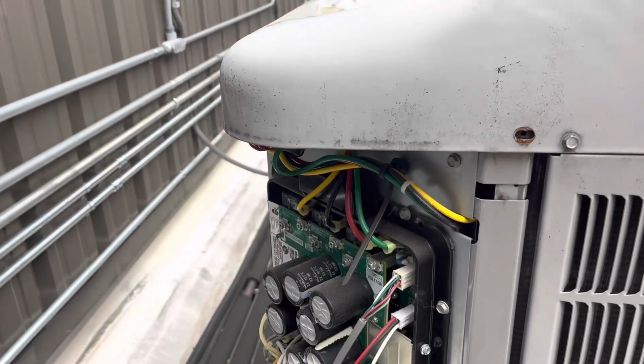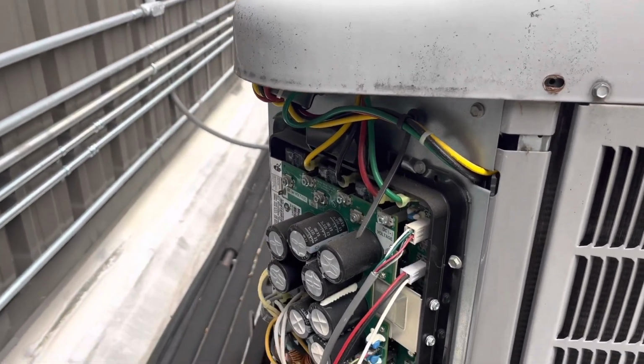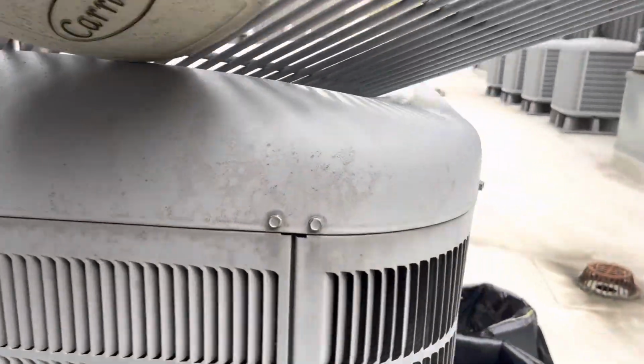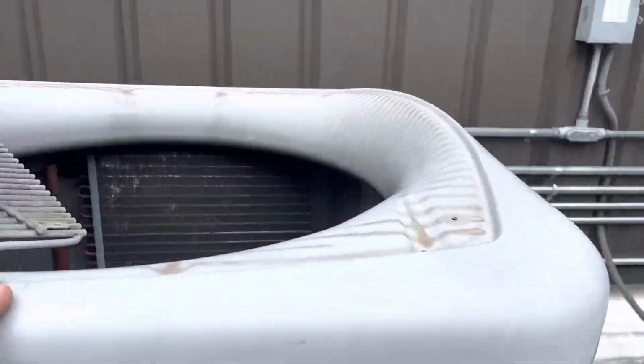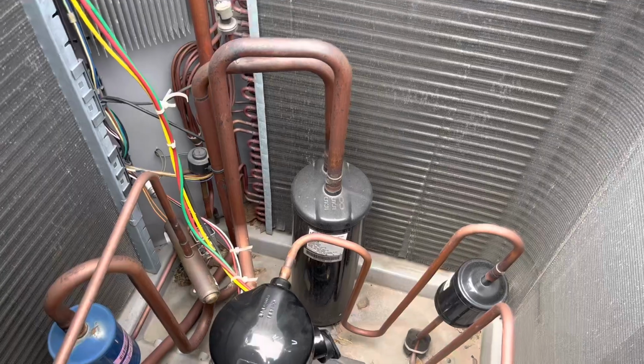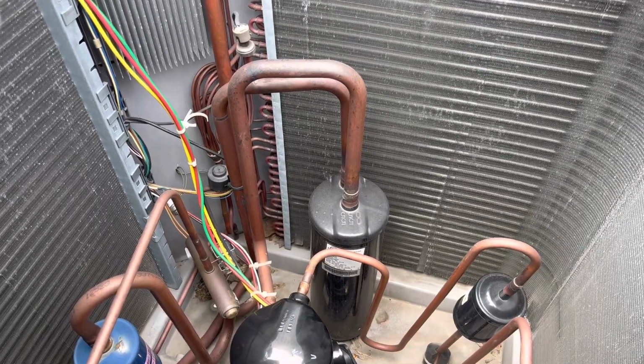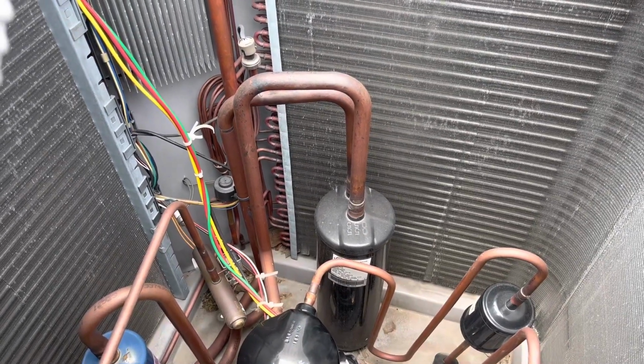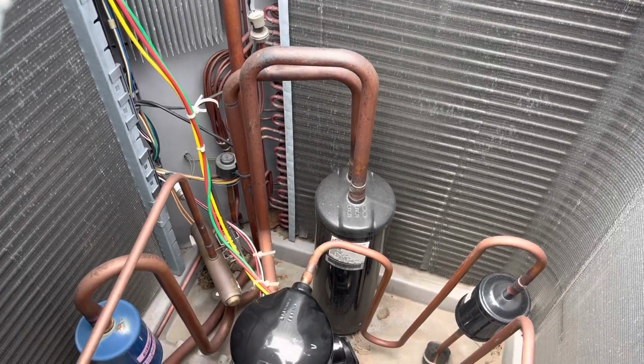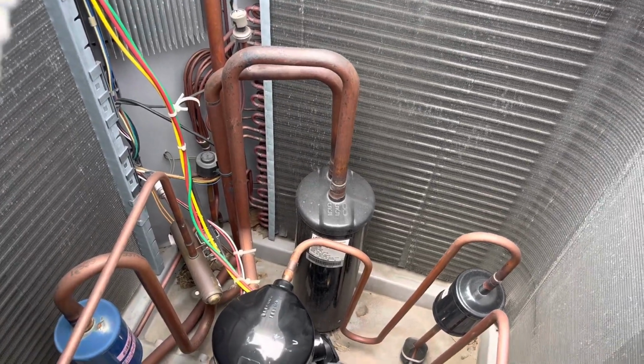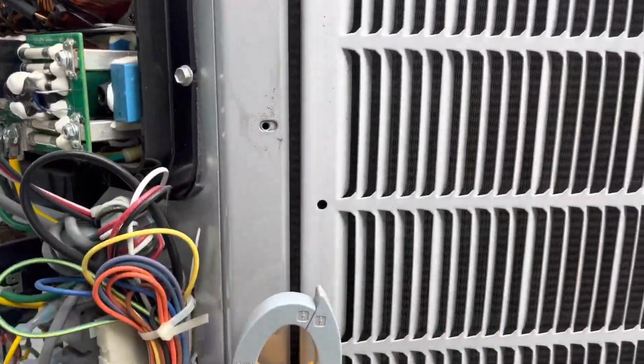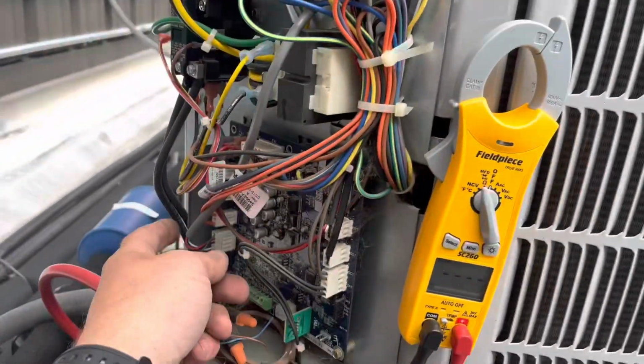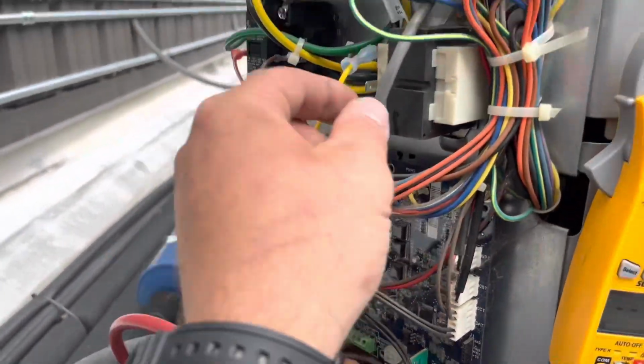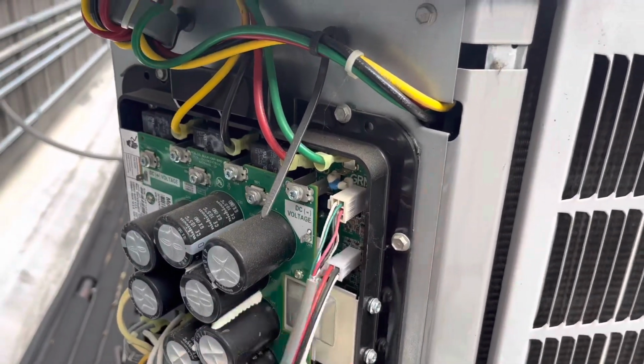But based on the prices for this board and this compressor for this year, it's probably cheaper to get a condenser or a heat pump inverter rather than replace it. It's 9 years old. But again, I'll have to price all that out for the customer and go from there. But let me see if my error code changes when I keep this unplugged. The only thing I have unplugged is the compressor, at the compressor, but not this PL1. This is for the other side of the compressor, which I believe is just the inverter board.